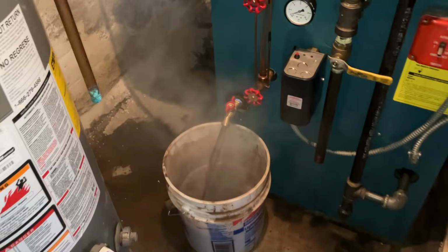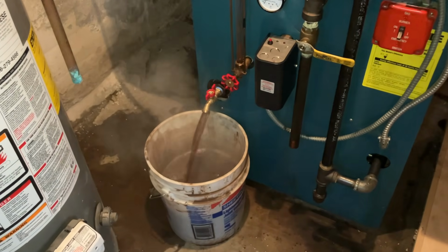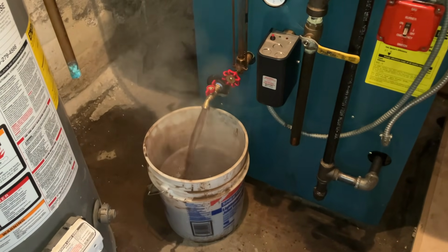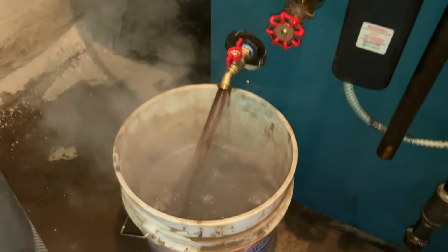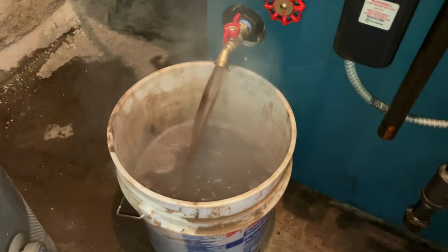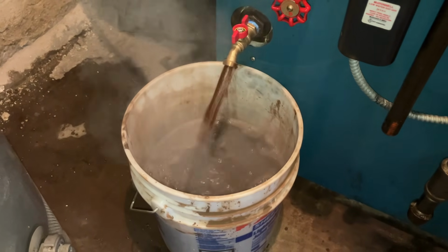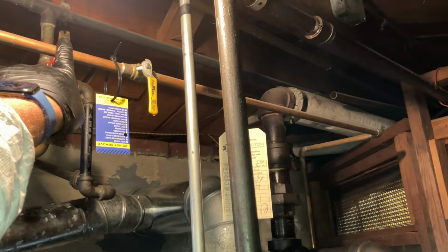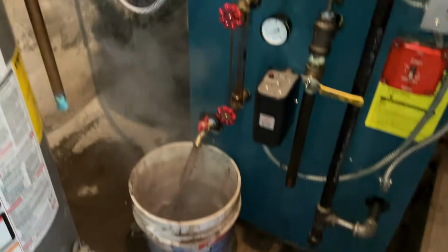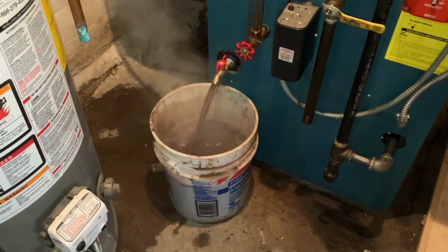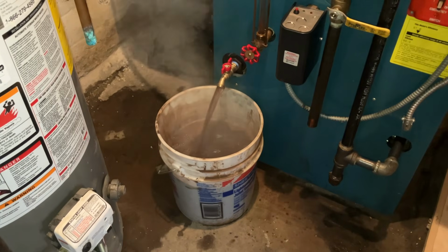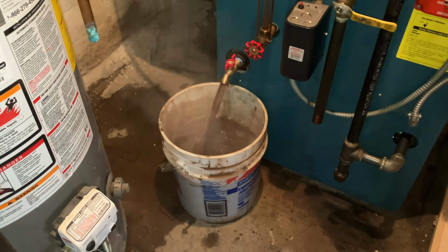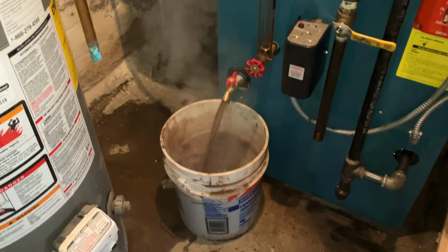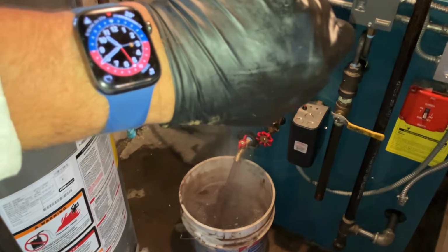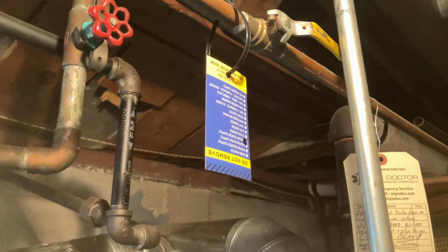I'm gonna kill power. I wanna drain this completely. I wanna flush out the bottom of this boiler with all that muck and all that sludge, which is just not really good for this system. Let's drain this out. We're gonna refill with some hot water from the water heater. Perfect, if it was cold water, would be cautious in doing so. We don't wanna crack or shock the boiler with that thermal temperature difference. All right, we're gonna clean this out a few times, so still got some time here. We're good. All right, refilling the boiler.